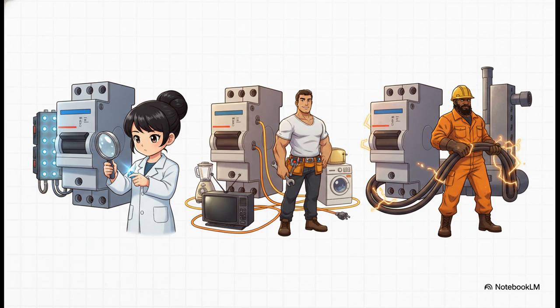So if you remember one thing, remember this: that little letter on your circuit breaker, B, C, or D, it's not a grade. It's not like A is better than C. It's a job description. It tells you exactly what that breaker is designed to do. And matching the breaker's job to the circuit's load is absolutely fundamental to electrical safety.